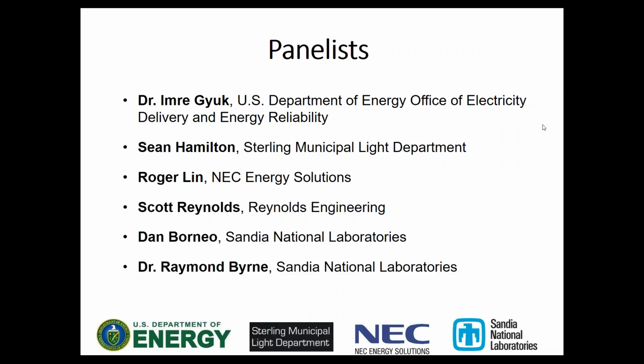I don't know the exact round trip efficiency of this particular project. In a peak load reduction mode, running at roughly a 2-hour rate, we've seen systems in similar applications with round trip efficiencies ranging from 80% to high 80s, including thermal management and losses within the battery, the power conversion system, and the transformer. In higher rate operation, round trip efficiencies typically drop, but I'd imagine this one is probably mid-80s. I'd have to check what our modeling guys penciled out for this one.